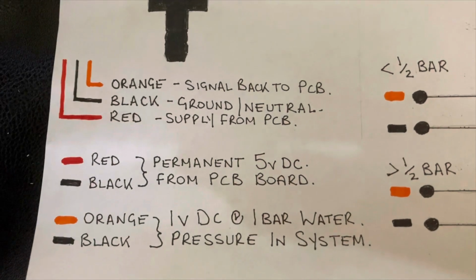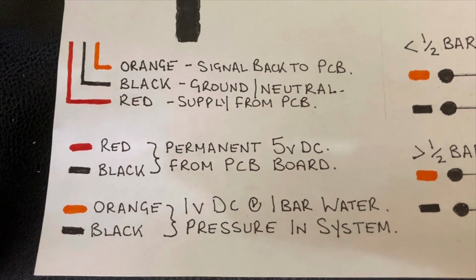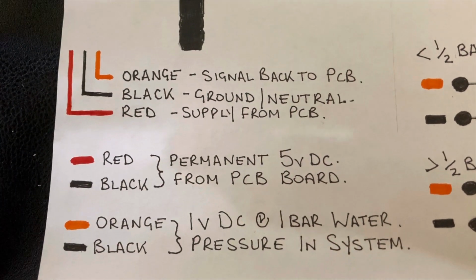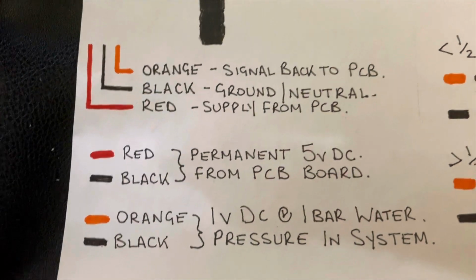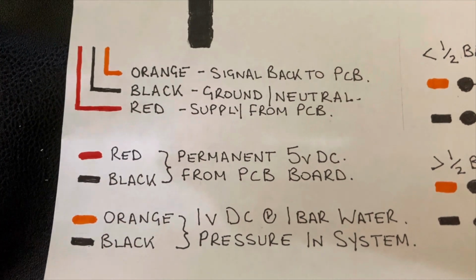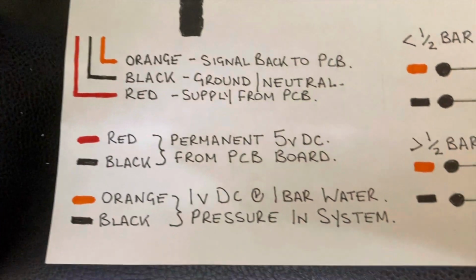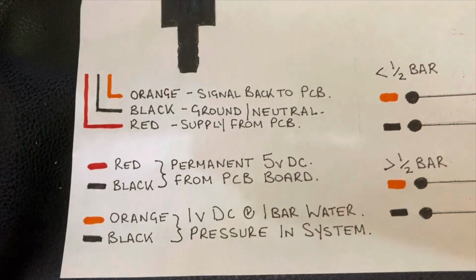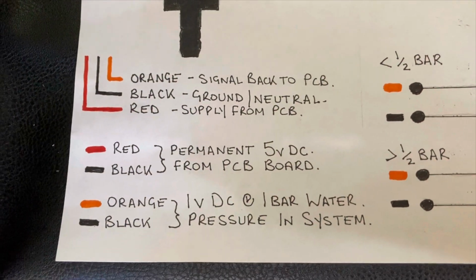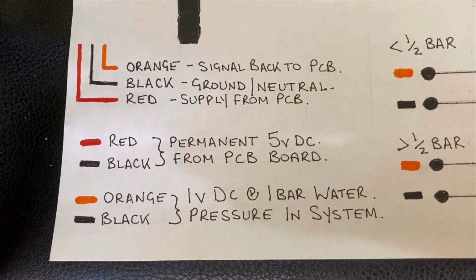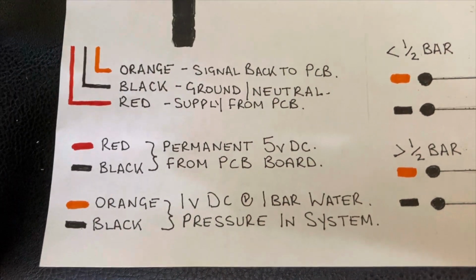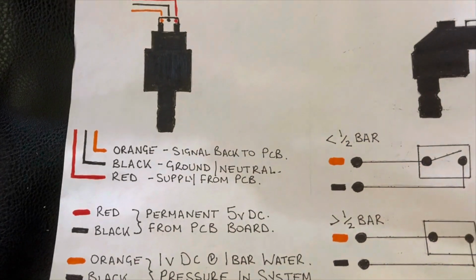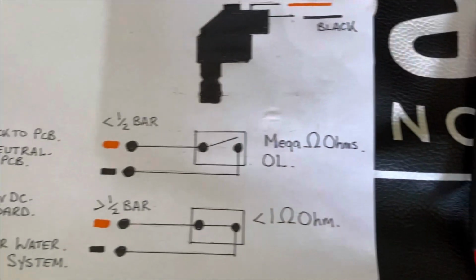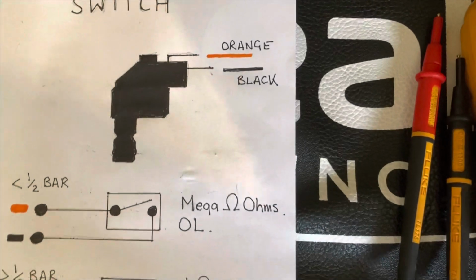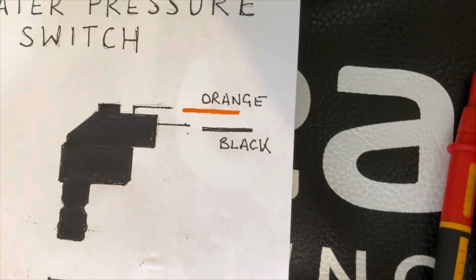I've never really had one fail, but they can get blocked, or you can just completely lose it, and you'll just probably get 5 volts back. And the boiler will probably still read low water pressure. If you've got a fault with the transducer, it'll probably still read low water pressure F1, even if it's sending 5 volts back. It just can't read it. So that's that. On the switch side, it's a bit different.